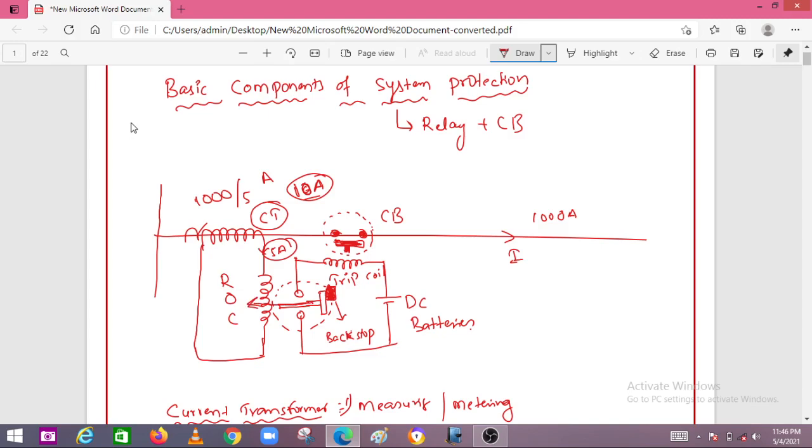By moving like this, this plunger will be closing these two contacts whenever it is moving to the left hand side. As long as it is closing these two contacts, the circuit is closed like this, and these batteries are connected to this relay operating or trip coil, and similarly as the ROC is energized, this trip coil will also be magnetized, and it will be attracting this plunger in the downward direction.